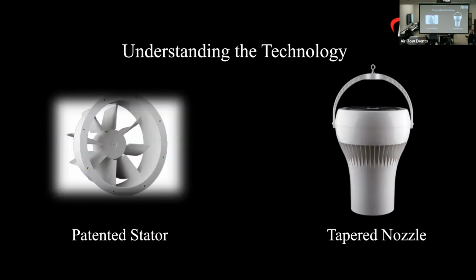Understanding the technology, what kind of sets us apart. Tom talked a little bit earlier at the very beginning about how we had come out with this type of destratification fan, and there's been some competitors that have come in since. What really sets us apart from that type of destratification is our patented stator and our tapered nozzle design, because what that does is it controls the air column. Makes it different. So once you have that controlled air column, you can actually set that up to design a system of fans for a particular space to have that air column go down. So basically what we can look at at that point is say, hey, this fan covers X amount of square footage.